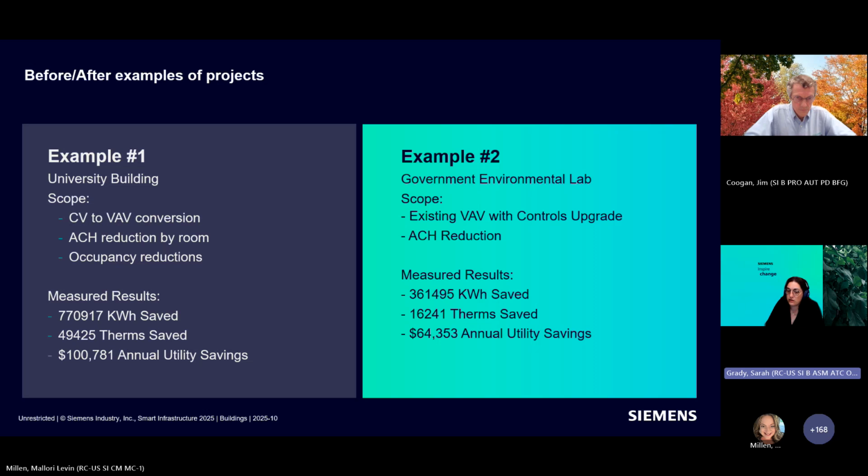We also did occupancy reductions. And this primarily comes into play with secondary ed because when you talk about occupancy reductions, it may seem like, okay, 40 hours a week you're occupied. Oftentimes the laboratories in universities, particularly the teaching laboratories, might be unoccupied as much as 80% of the time. And this is because you have summer breaks, you have winter breaks, you have teaching schedules, so you might only have people in there a couple hours during the day.